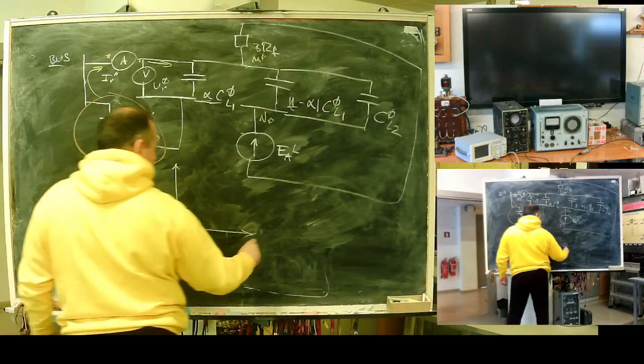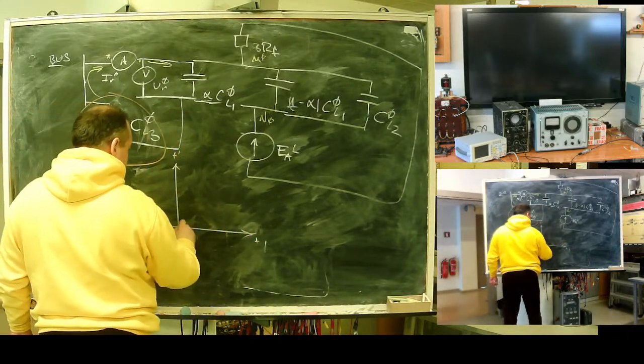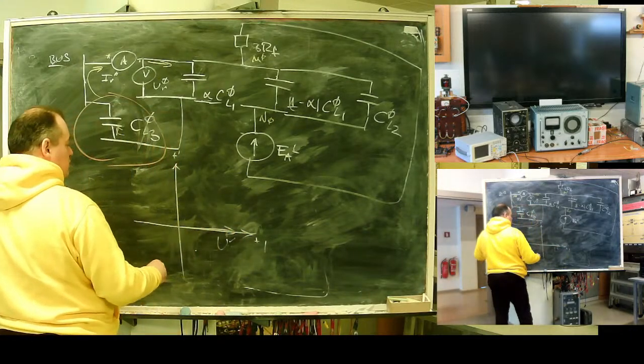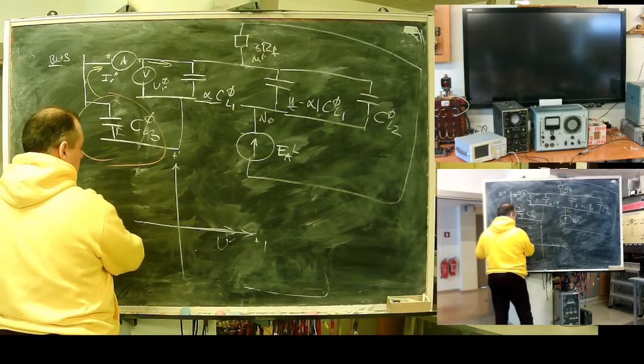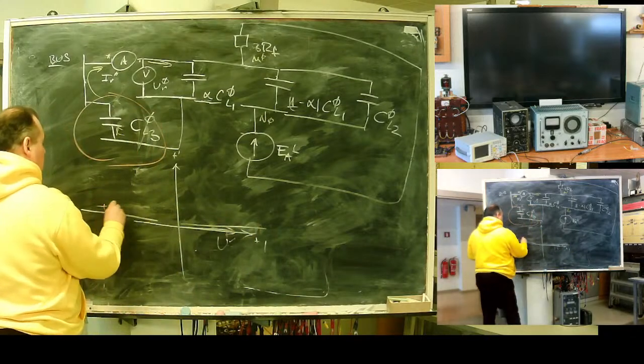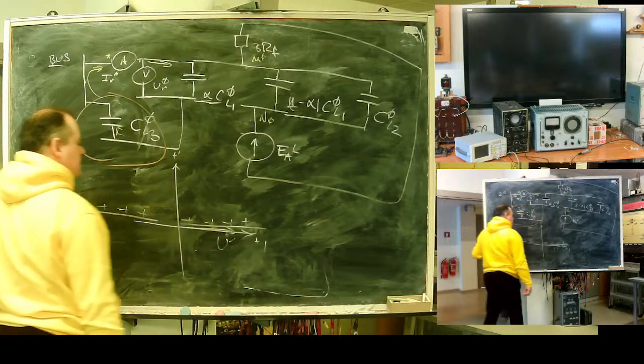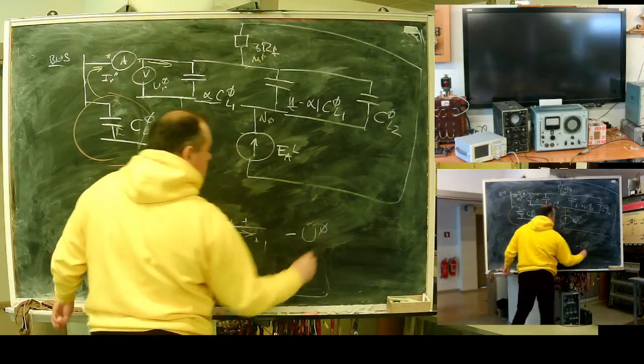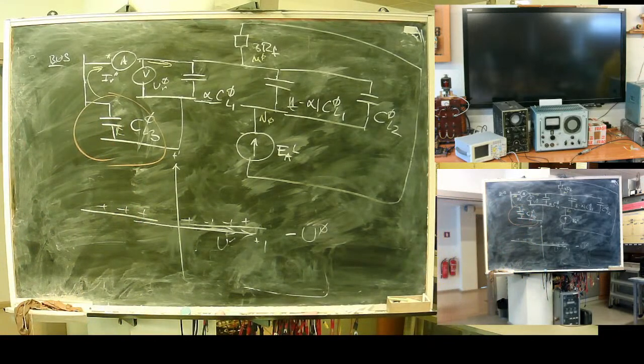Actually, your characteristic here is your voltage. Your characteristic in general can be something like this, where polarizing is minus or 0. Actually, read very carefully manual for your particular relay. There are relays using 0 sequence voltages and relays using minus 0 sequence voltage. Read manual. Your particular relay is operating from what? Here is the current, not current, but direction characteristic.